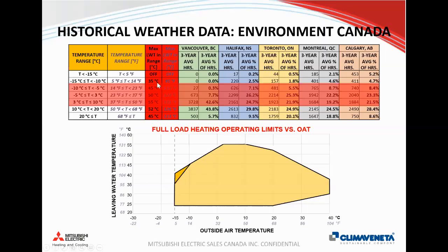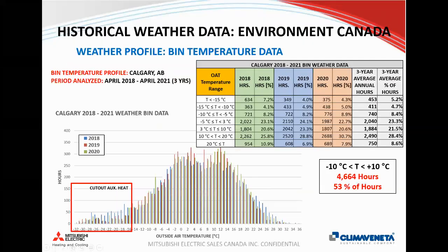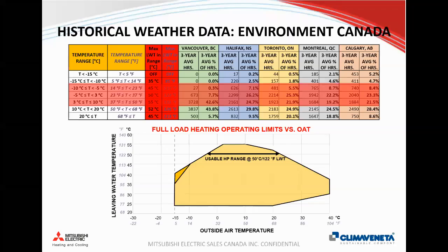And for any designers on the call, typically you want to pick a fixed supply temperature for the system. You don't want to have a bunch of different operating conditions. Well, if it's condition A, then I'm going to have a supply temperature of X, but if it's condition B, I'm going to have a supply temperature of Y, and so on. You're going to typically just pick one supply temperature and stick with that. So for the air-to-water heat pump, this is why you will typically just want to look at what's referred to as a bivalent temperature. But again, really one of the other key takeaways from this presentation is to think about heating systems generally and how to incorporate air-to-water heat pumps into those systems.